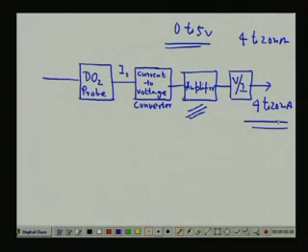Moreover, you see that we have used a plot. We made these measurements in bioreactors in the bioprocess instrumentation lab at IIT Kharagpur, and we found that we got consistently good results. When we measure with other sensors, there is a slight offset, which is quite obvious. So, this galvanic electrode worked very nicely in our laboratory, right.